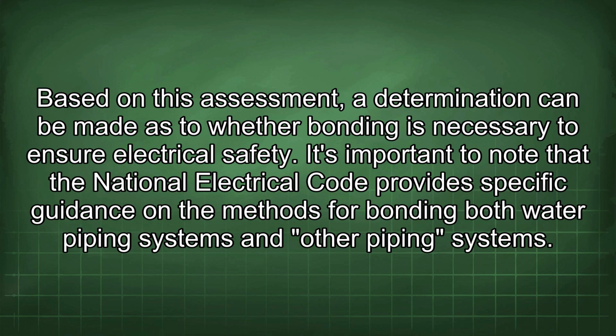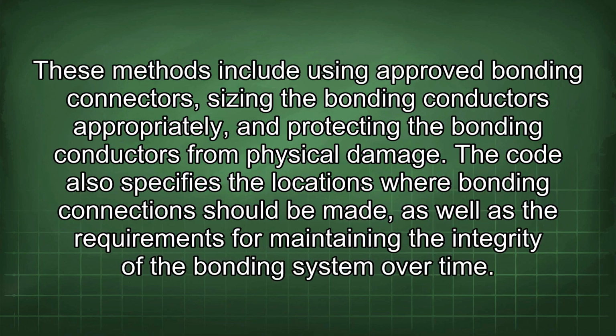It's important to note that the National Electrical Code provides specific guidance on the methods for bonding both water piping systems and other piping systems. These methods include using approved bonding connectors, sizing the bonding conductors appropriately, and protecting the bonding conductors from physical damage. The code also specifies the locations where bonding connections should be made, as well as the requirements for maintaining the integrity of the bonding system over time.